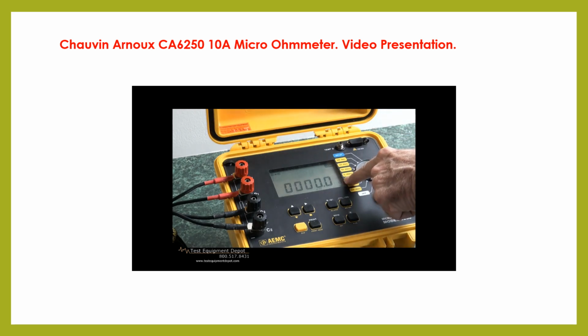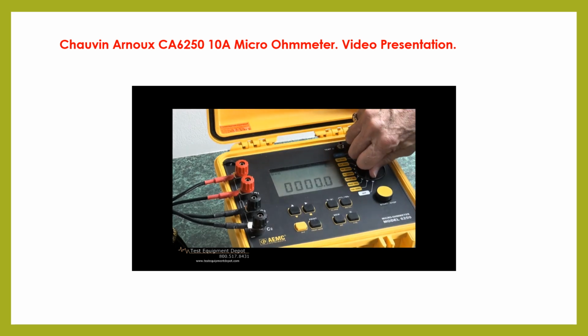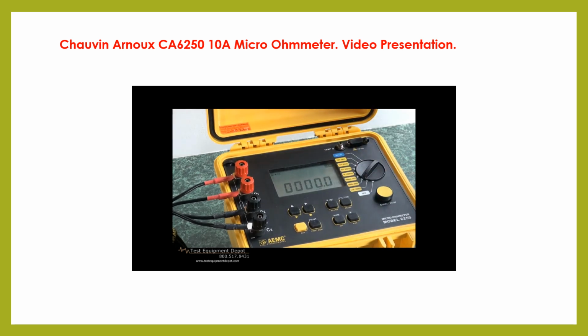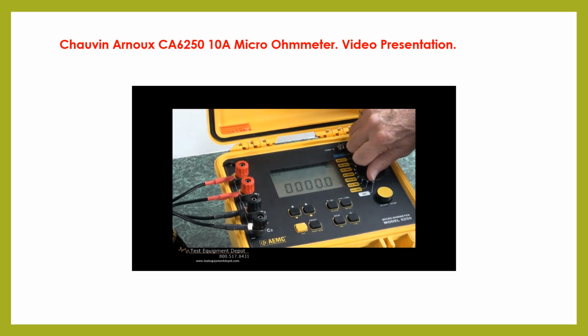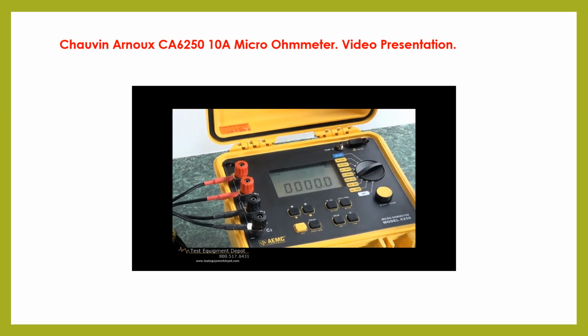First of all, it tells us we're on the ohm scale and we're only at 1/10 of an ohm range. Now that tells us that we are further on down scale, so we'll move it up with more sensitivity. We'll run a little more current through here, 10 milliamps, and try again. Aha, we're still reading all zeros, so it says that we have 0 ohms resistance, very low. Let's crank up the test signal to 100 milliamps. Now notice you get the operator and immediately it'll go back into standby. We're still reading all zeros, so it says we're way low.